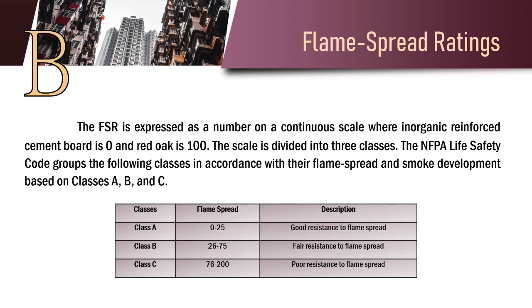The NFPA Life Safety Code groups the following classes in accordance with their flame spread and smoke development, based on classes A, B, and C. In the table, Class A has a flame spread of 0 to 25 and is said to have a good resistance. Class B has a flame spread of 26 to 75 and has a fair resistance, and Class C has a flame spread of 76 to 200 and has a poor resistance.